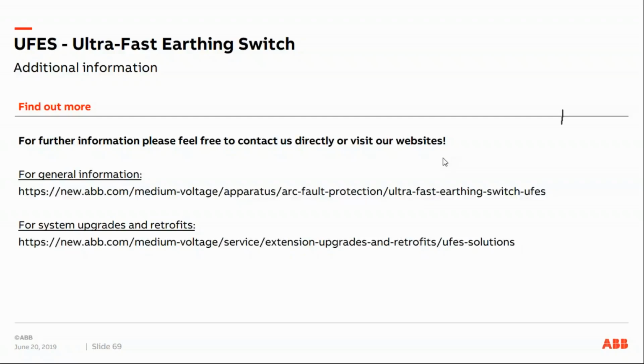Another question. Does the UFES also trip the breaker while shorting to ground simultaneously? Well, it's in one of the slides where I showed the simultaneous tripping operation. There you could see that it's optional. You can also give a tripping signal to the circuit breaker after the UFES has tripped for the fault clearance. Can the unit be repaired, or should it be replaced after every use? Yes, this is a one-shot device. It has to be replaced after it has tripped.